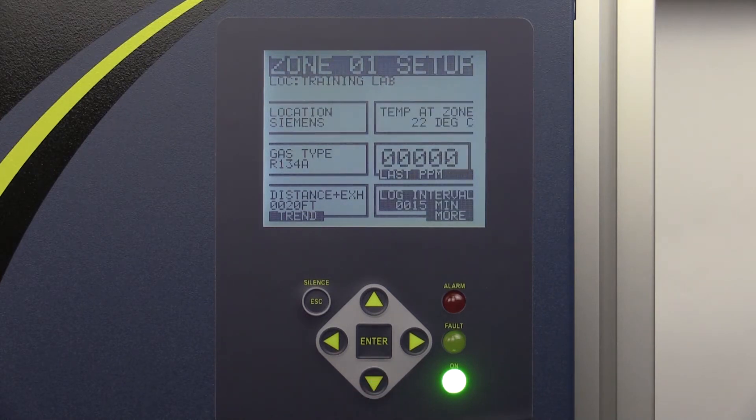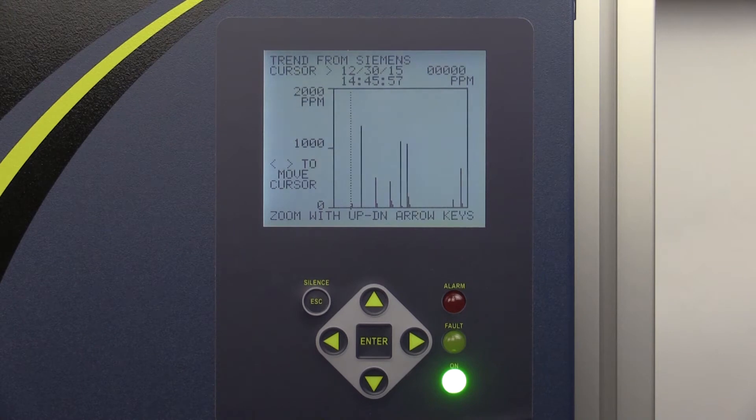Measure the air temperature in degrees Celsius at the specified zone and enter this value into the Temperature at Zone tab. The Last PPM tab displays the most recent PPM reading that was taken for that zone. The Log Interval tab allows you to set how often a PPM reading will be entered in the data log for that zone. The highest PPM reading during an interval will be entered into the log. The Log Trend graph can be accessed by scrolling down to the Trend tab and pressing Enter. The graph displays the last 100 logged PPM readings for that zone.